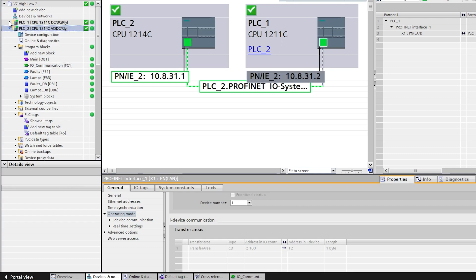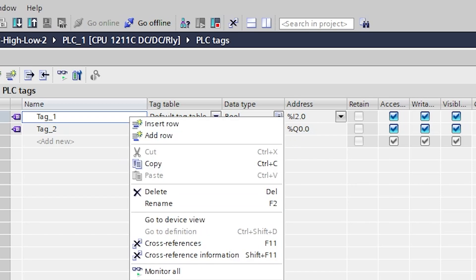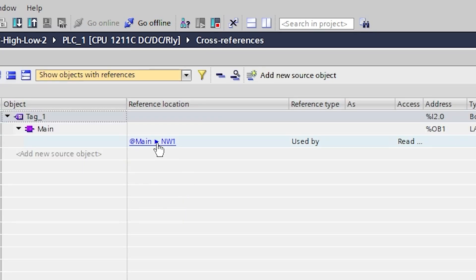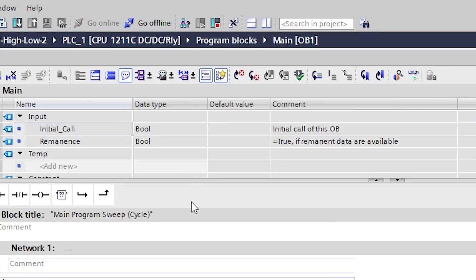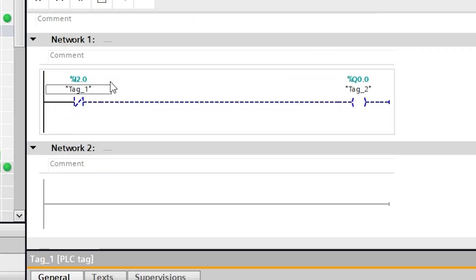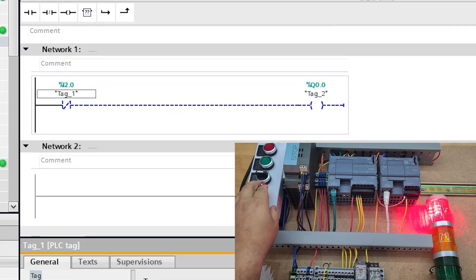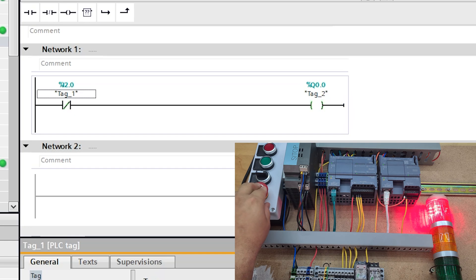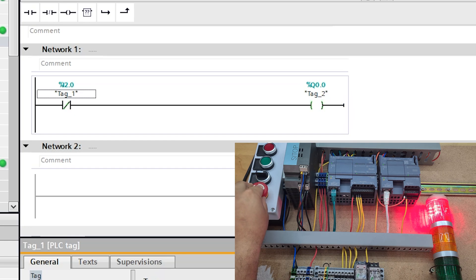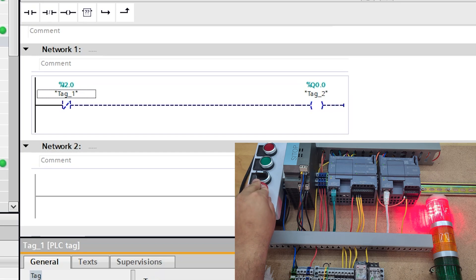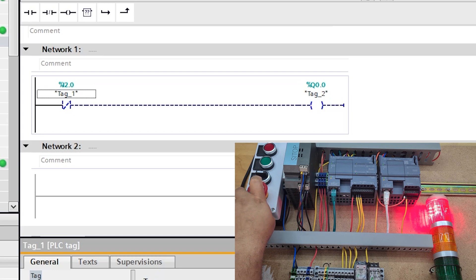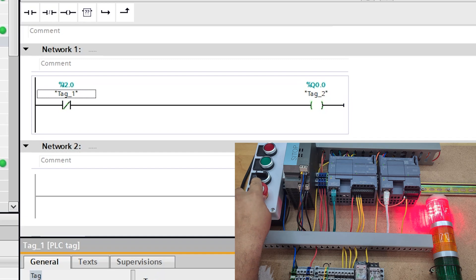Now if I go to PLC1, show all my tags, I've got input 2.0 which I've just left as Tag_1. Cross-reference that, see where it's used - it's using Main. Now I'm saying okay, when we don't have that input 2.0, then trigger output Q0.0. Output Q0.0 is just my buzzer. When I don't have input 2, if I lose that you can see there I've lost my signal for my E-stop, and then now you can see this is on the second PLC - it is now triggering that output tag Q0.0.